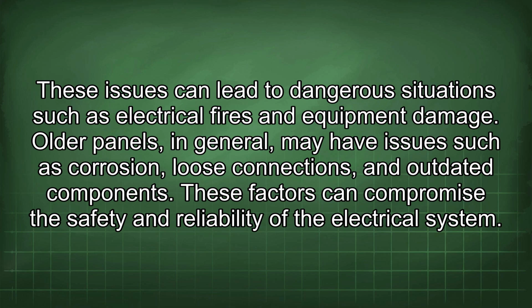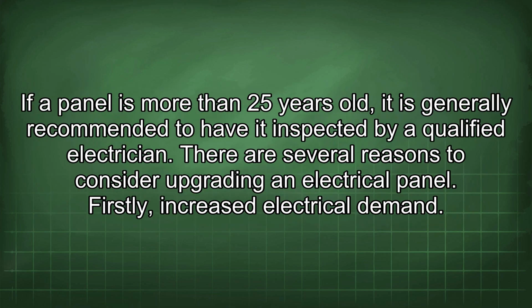Older panels in general may have issues such as corrosion, loose connections, and outdated components. These factors can compromise the safety and reliability of the electrical system. If a panel is more than 25 years old, it is generally recommended to have it inspected by a qualified electrician. There are several reasons to consider upgrading an electrical panel.